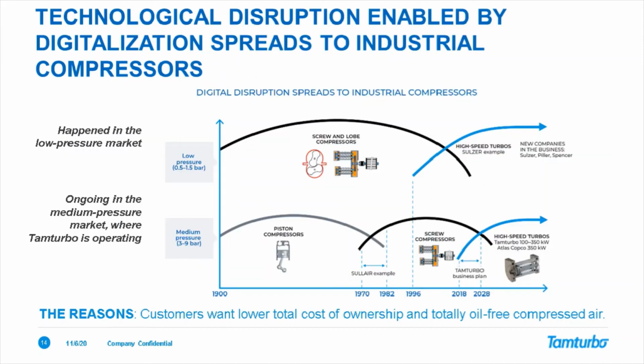As said, this already happened in the low pressure market, which you can see on the top there. Since the 90s, the high speed blowers started to take the market from the screw and lobe blowers and compressors, and now the same is happening with the industrial medium level compressors, so from 3 to 9 bar range, and we are pretty much the only one actively selling this technology at the moment.